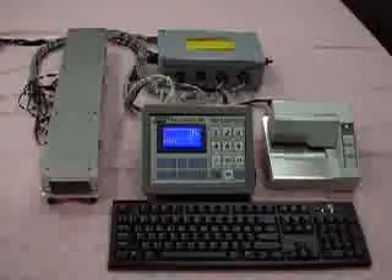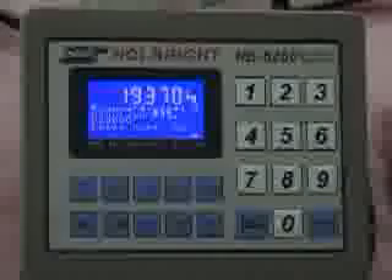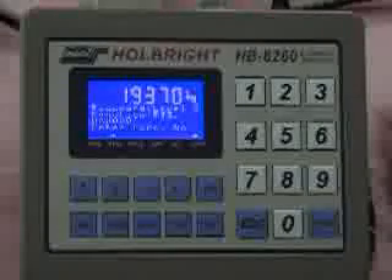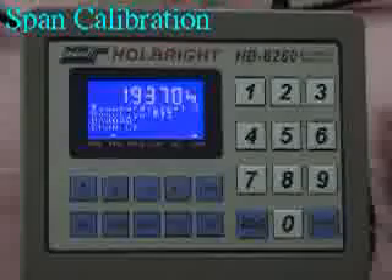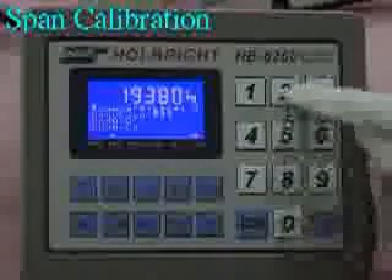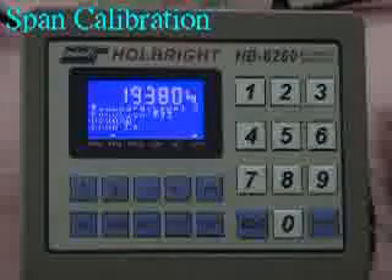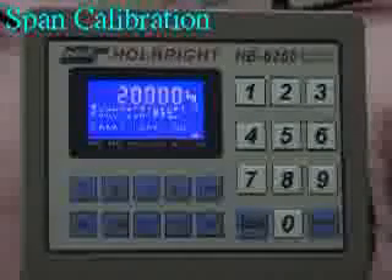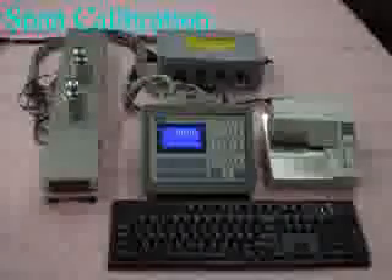Now we place two standard test weights of 10,000 kg each on the truck scale. Press Enter to enter the standard test weight setting. Enter 20,000 kg. Press Enter to confirm. The HB-6260 revises the weighing value to 20,000 kg and completes the span calibration.